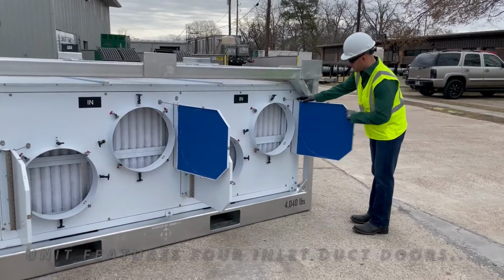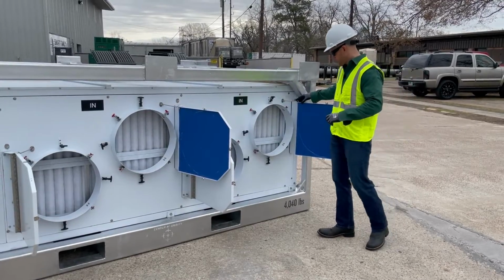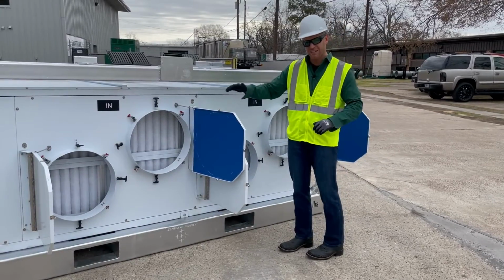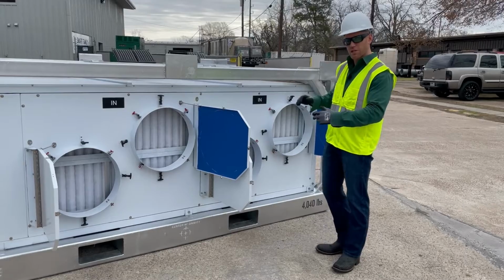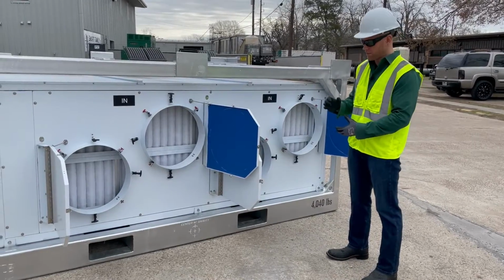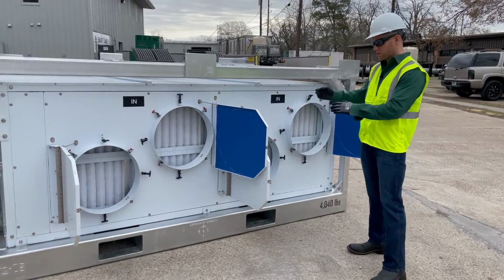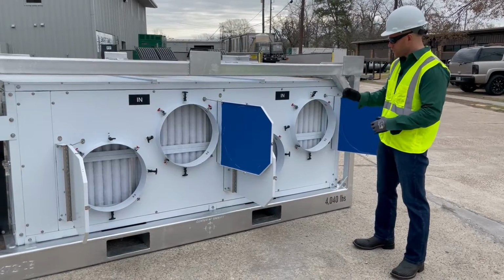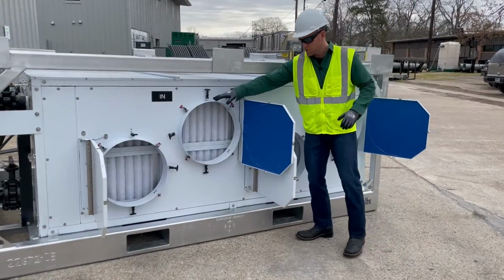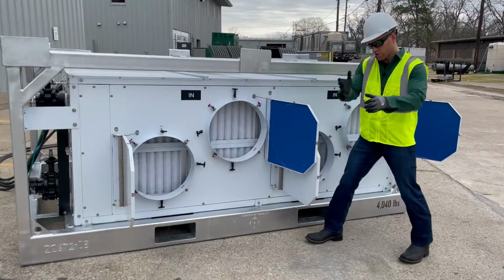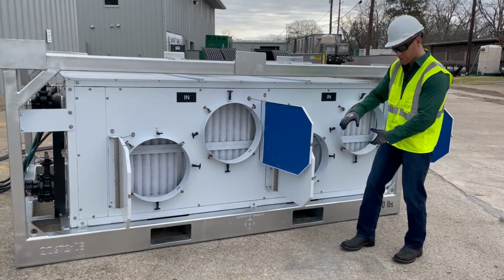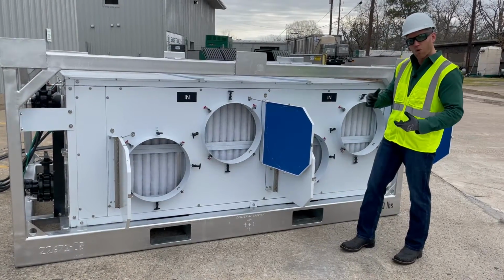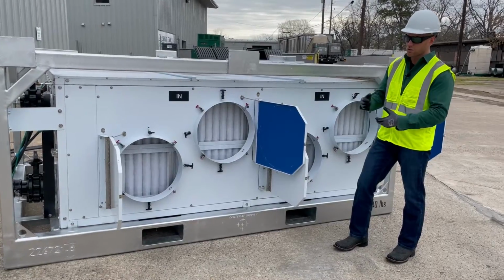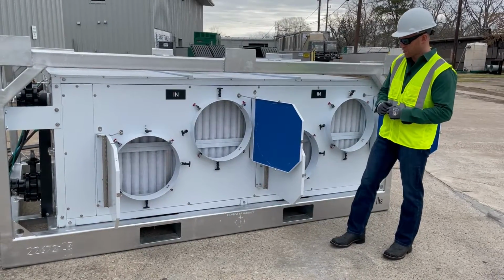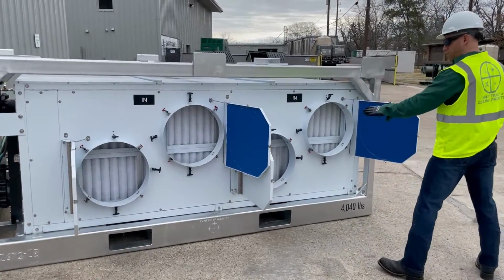And typically, you want to have all of your inlets or all of your return air duct connections open. That's because we never want to starve the unit. This particular model and most Smart Family models, you can run open to the ambient or outside air, or you could duct return air ducts and run return air from the space, or you can run a mixture. That's totally dependent upon the job site application. Okay? So we opened up our 4 inlets.